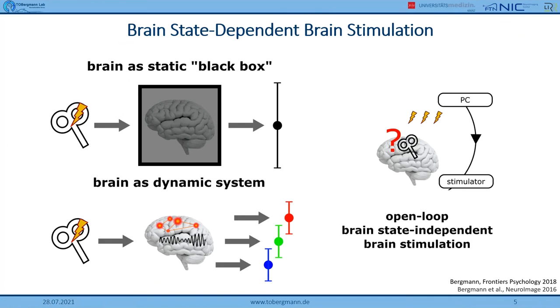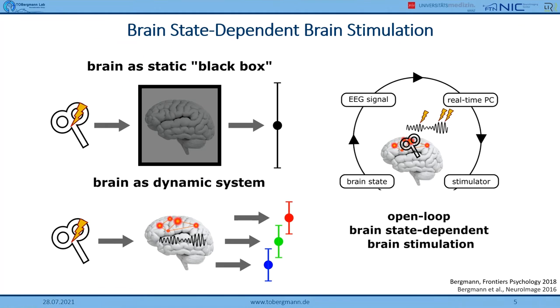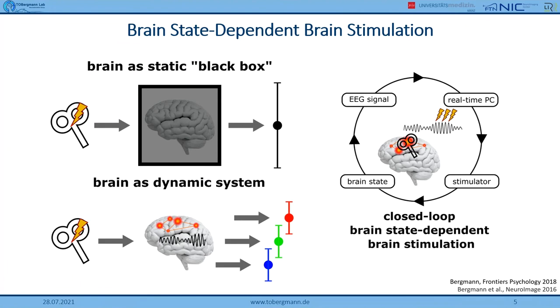For open-loop brain state-independent stimulation, we trigger the stimulator at any time independent of brain activity in a randomized fashion. For brain state-dependent stimulation, we take into account the brain state — for example, providing an EEG signal, looking at the amplitude and phase of a target frequency, and analyzing it in real time. We can then configure and trigger the stimulator at a certain time. Closing the loop — where we actually modify the brain states we are monitoring — is what we are aiming for in the future. Open-loop brain state-dependent stimulation is what we are doing already right now.